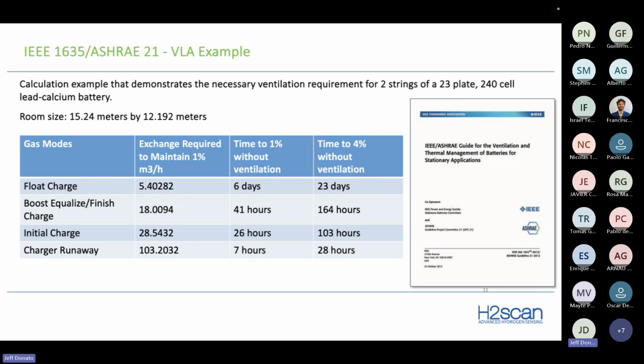And this is where we find a lot of facilities are connecting their hydrogen sensor to a relay that will turn on or off a fan. That's a very good idea, just because it's something that happens automatically, and it's very easy to set up with the correct equipment. And also, when you get a notification that the ventilation system turned on at 1% hydrogen, you can simply monitor to make sure that the hydrogen is being evacuated properly. It's a monitoring situation and not necessarily having to take a lot of action.